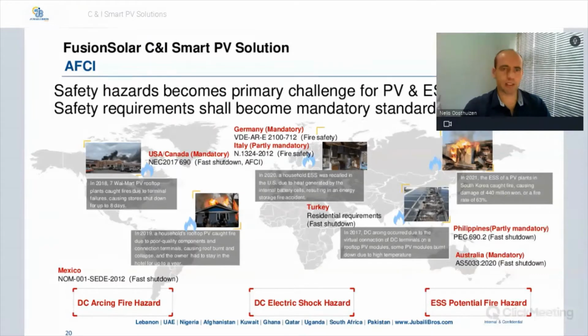Safety hazards have become the primary challenge for PV and energy storage systems. Safety requirements shall become mandatory standards. In this slide here, you can see various instances of PV plant failures. These plants are not necessarily Huawei plants, but plants in general where fires or hazards have occurred. I know in South Africa, we recently had a big fire at one of the popular estates, where it was actually a battery management system that failed. But again, it was a DC arc that caused the fire. So a lot of countries are now incorporating mandatory standards to ensure that PV systems are all safe and up to standard.